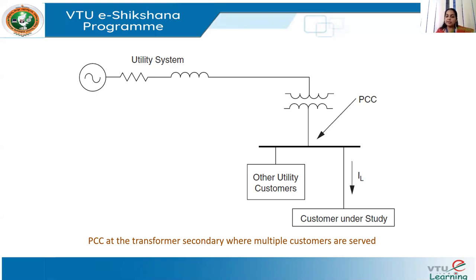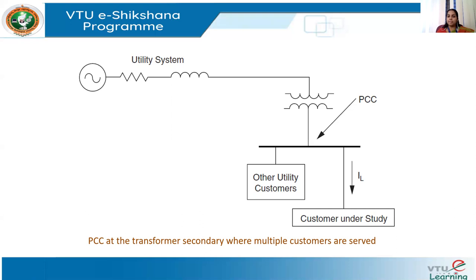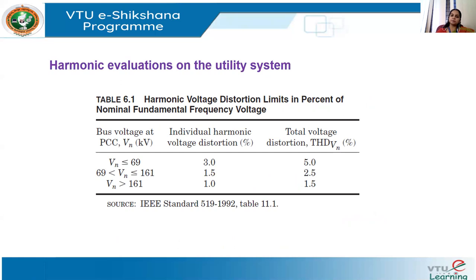The concept of PCC is now clear — where to locate the PCC and that PCC is the point where evaluations are done. When talking about harmonic evaluation, we can do it either on the utility side or on the end user side. The harmonic evaluations on the utility system involve procedures to determine the acceptability of voltage distortion for all customers. There is a table giving the THD value for different voltage levels.